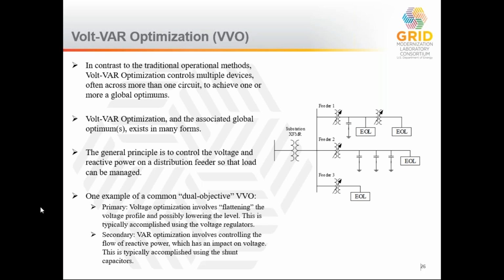However, to do that properly, you have to understand that when you engage all of these new assets, how will they be interacting with the historical assets such as the voltage regulators and shunt capacitors? Because if not implemented properly, you can decrease the life of that equipment and in some cases damage it or even cause it to misoperate.